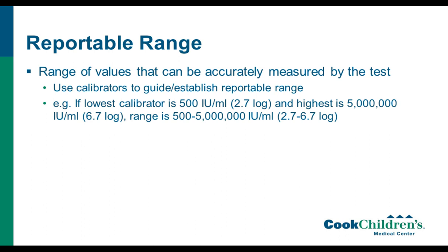The reportable range is also required for both FDA-approved and FDA-modified LDTs. And this is the range of values that can be adequately or accurately measured by the test. And so when you're using your calibrators, that's really going to help guide or establish your reportable range. You want to stay within the highs and lows of your calibrators.